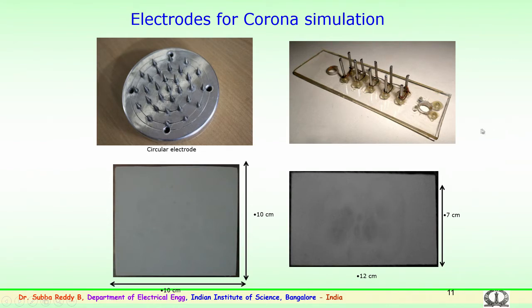Needles are not employed here. So, we try to simulate the corona over a period of time, and the discharges are continuously impinged on the sample. This is the flat rubber sample, the actual material used for manufacturing insulators. It will be impinged over a period of time, and the surface degradation is analyzed and studied.